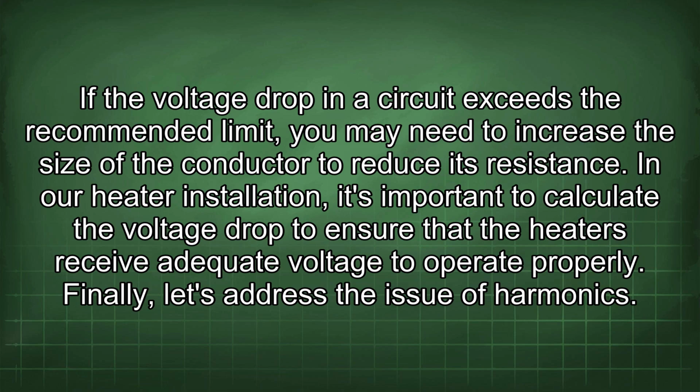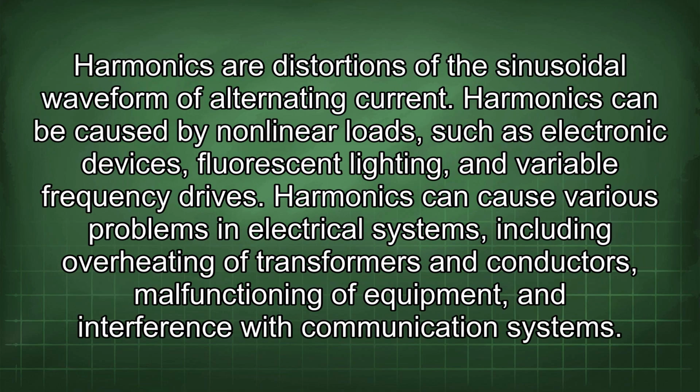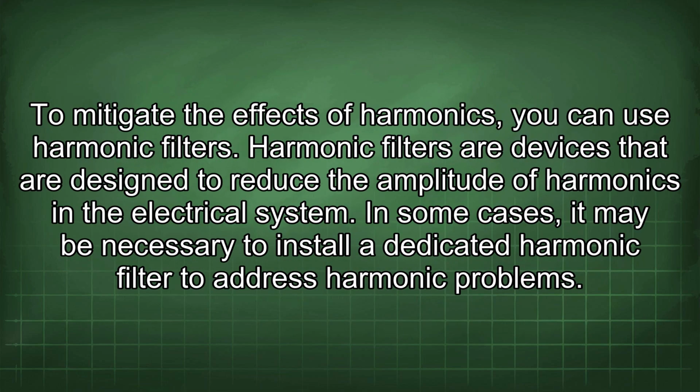Finally, let's address the issue of harmonics. Harmonics are distortions of the sinusoidal waveform of alternating current. Harmonics can be caused by nonlinear loads, such as electronic devices, fluorescent lighting, and variable frequency drives. Harmonics can cause various problems in electrical systems, including overheating of transformers and conductors, malfunctioning of equipment, and interference with communication systems. To mitigate the effects of harmonics, you can use harmonic filters.